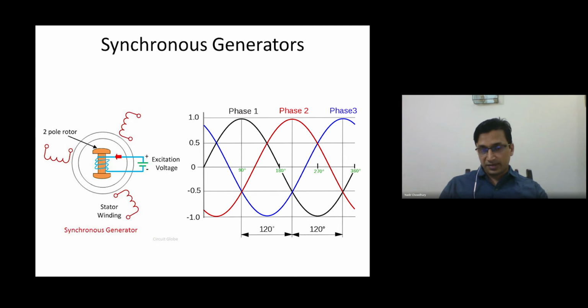Modern power systems are very much automated and smart. A gas turbine can take care of itself, so the controller handles it. We just give the command. But behind the scene, when we try to reduce reactive power, the excitation voltage is reduced, the excitation current and magnetization become less, so the flux cut is less, and that's why less power is generated.